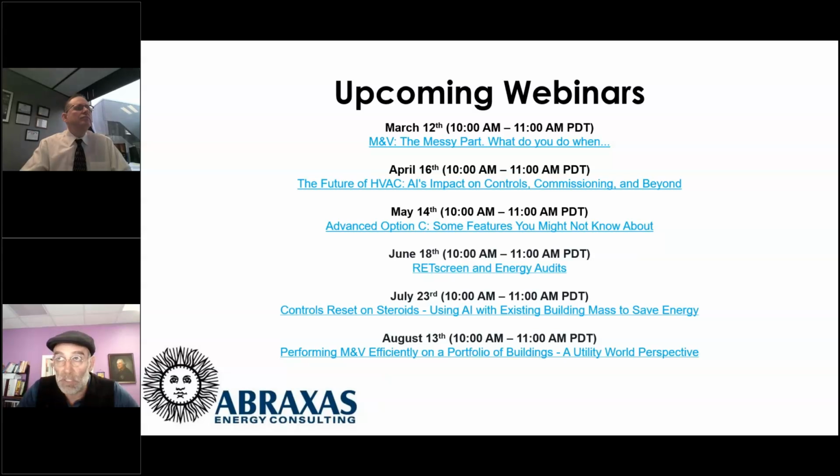What's not looking right? You look at the BAS front end. It's like, oh my gosh, look at that. That's not working. That's not working. Look at this. But mostly, I think it's trend logs, and you can find out there's no lockout. They're not resetting. There's no setback. And why is this air handler running all the time? That's stupid. And that kind of stuff. And so then you come up with these measures.